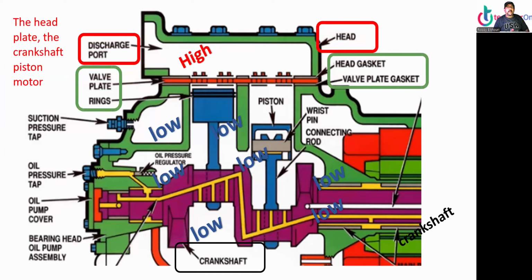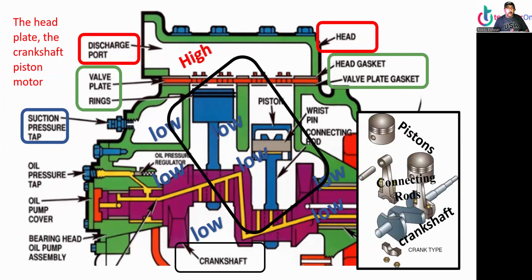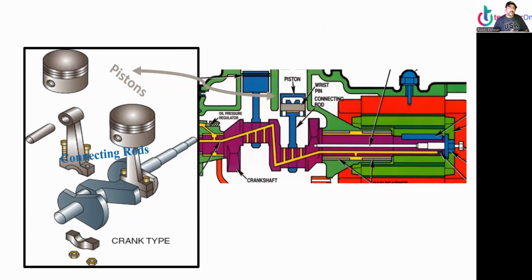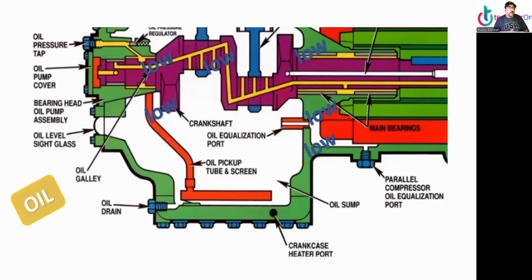We have the valve plate, head gasket, valve plate gasket. Those we can remove, take apart, fix, put back. I'll explain in a while. Suction pressure tap. This is where you check the low pressure. And inside here is the piston, connecting rod, and crankshaft. All right, now piston, connecting rod, crankshaft are inside there. Okay, and crankshaft.